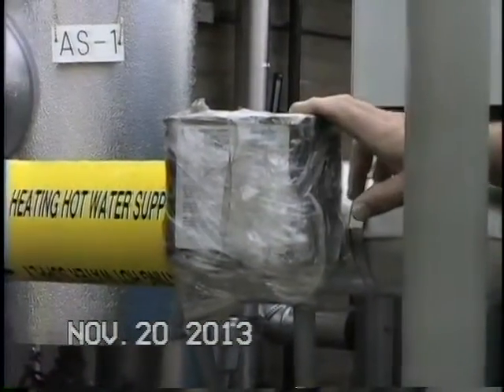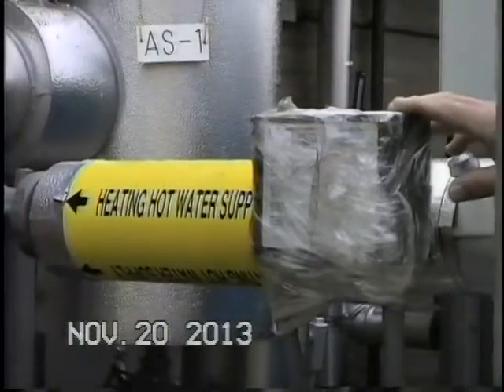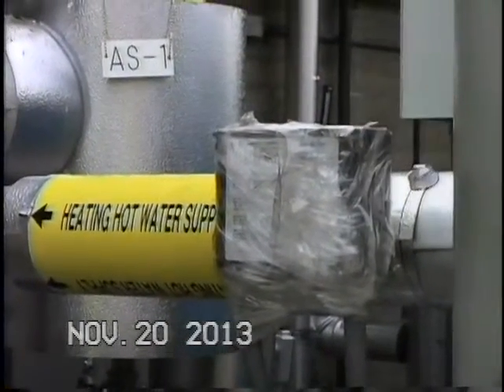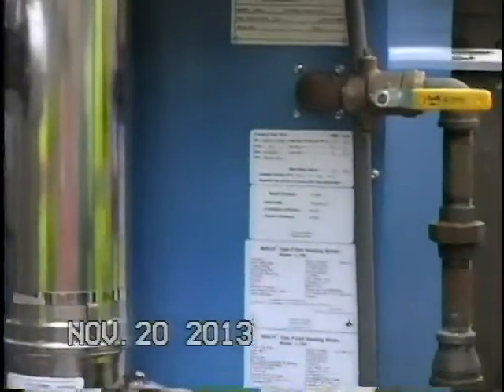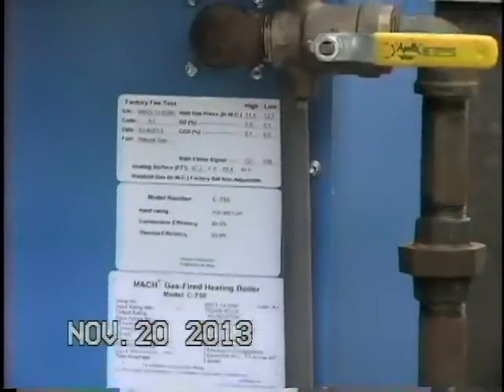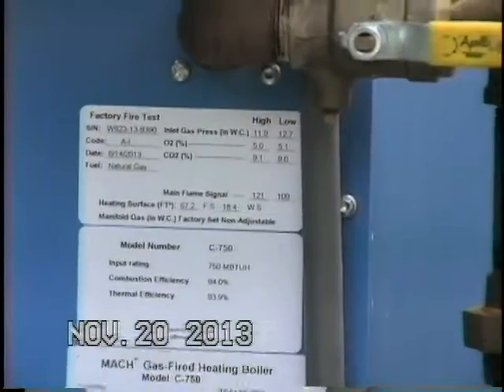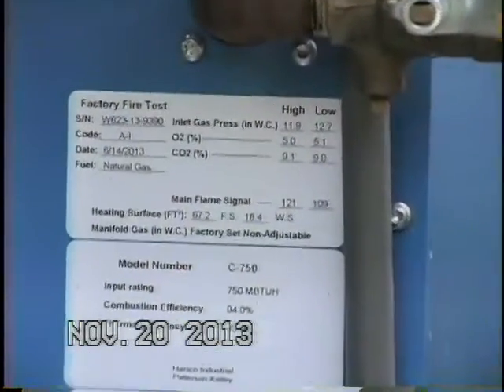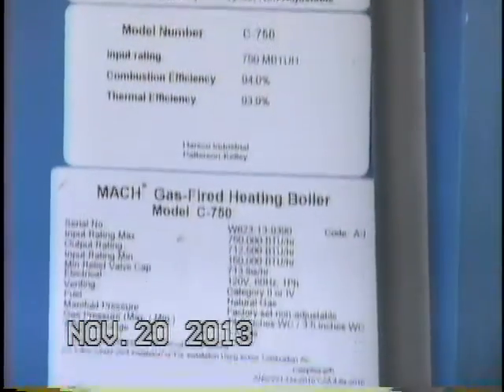This is a low water cutoff. The cover is missing. We'll send the cover, and Dawson is going to replace it. That needs a cover on there. Anything else on this side? Here, again, here's your gas shut off to the boiler, and that's about it on that side.